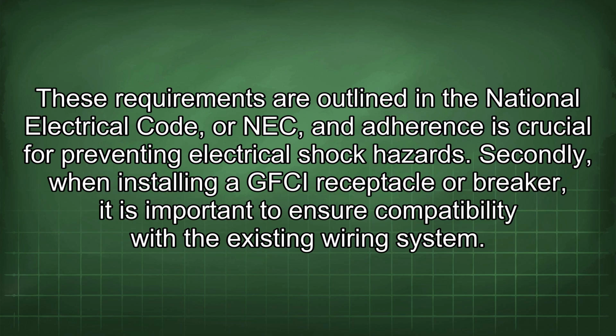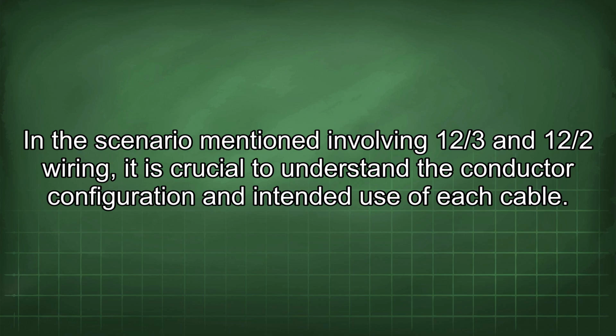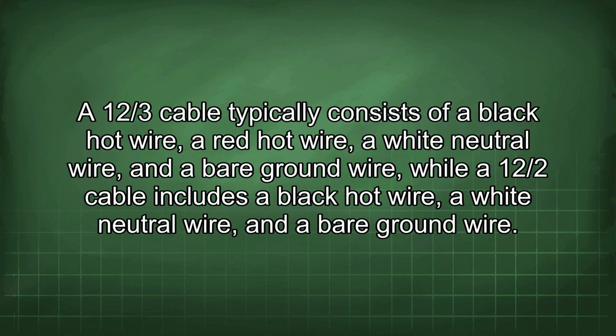Secondly, when installing a GFCI receptacle or breaker, it is important to ensure compatibility with the existing wiring system. In the scenario mentioned involving 12/3 and 12/2 wiring, it is crucial to understand the conductor configuration and intended use of each cable. A 12/3 cable typically consists of a black hot wire, a red hot wire, a white neutral wire, and a bare ground wire, while a 12/2 cable includes a black hot wire, a white neutral wire, and a bare ground wire.